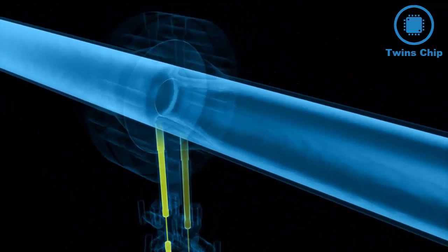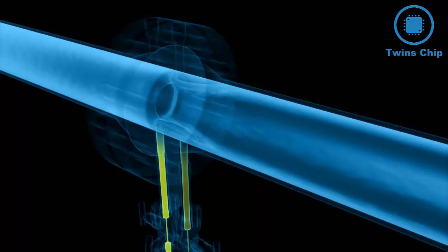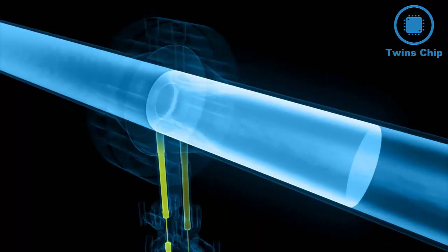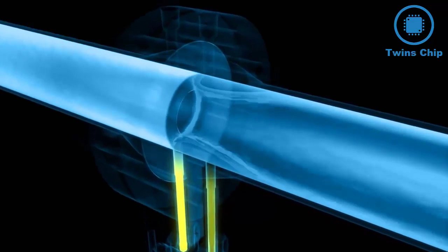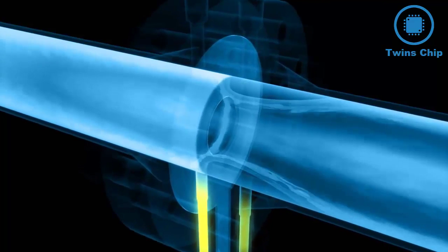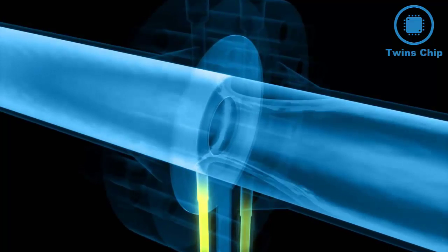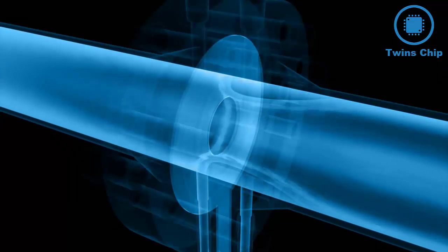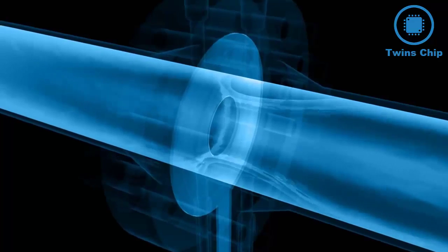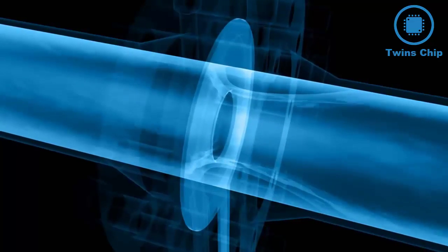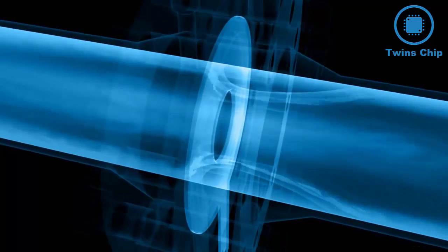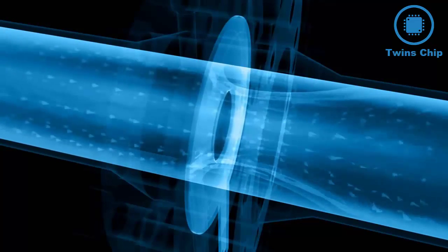This pressure difference is a direct measure for the flow velocity, and thus the mass and volume flow in the pipe. The higher the flow velocity, and the resulting drop in pressure around the orifice plate, the greater the differential pressure measured. In numerous industrial applications, the orifice plate covers many needs of flow measurement technology. However, other designs are available for certain measuring tasks to minimize undesired effects, such as excessive pressure loss or abrasion of components due to solids carried in the fluid.